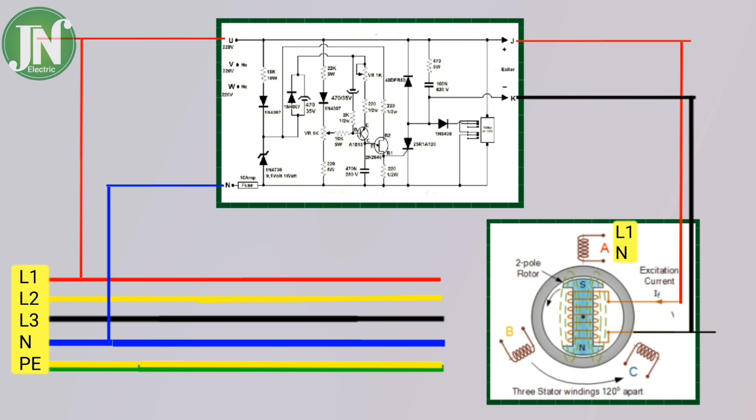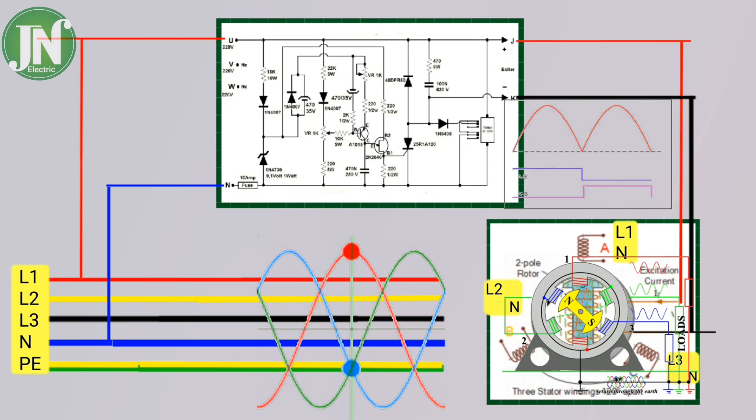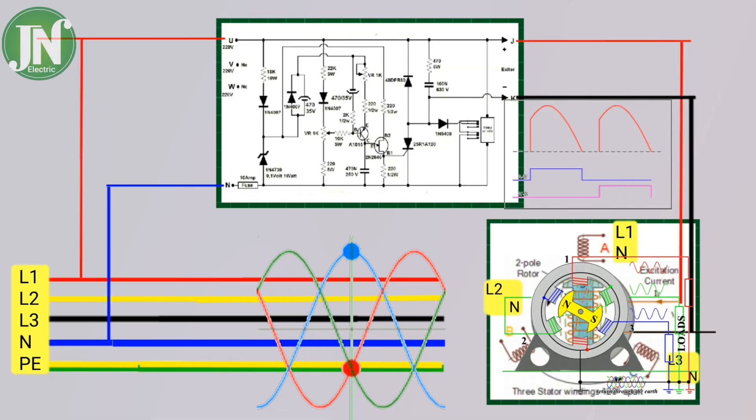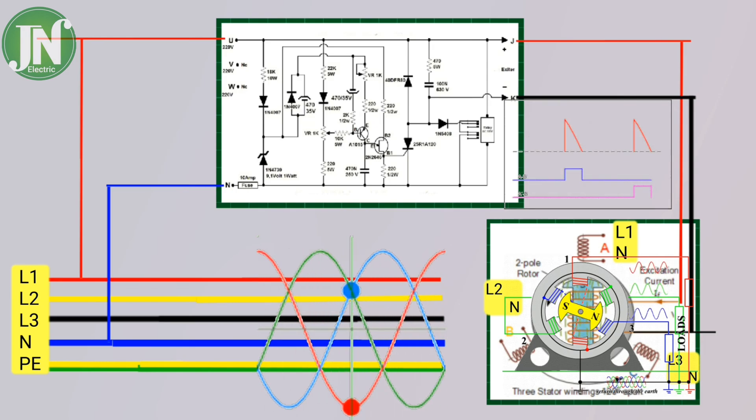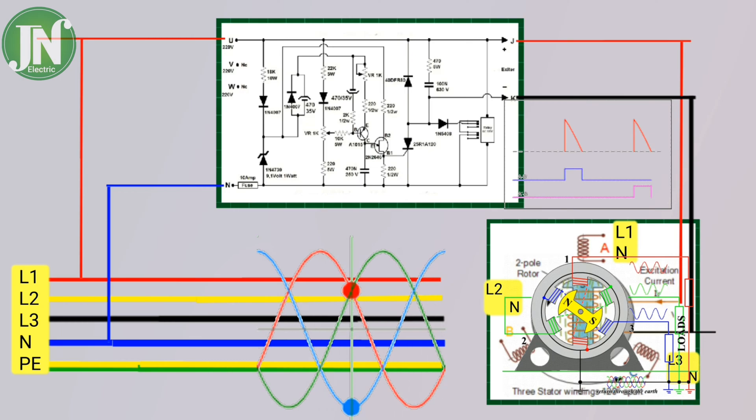This produces a low voltage DC signal that is proportional to the AC generator voltage. This actual DC signal is compared with a set DC value produced by the reference circuit of the zener diode and resistor.